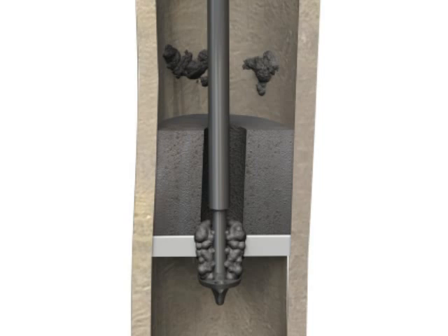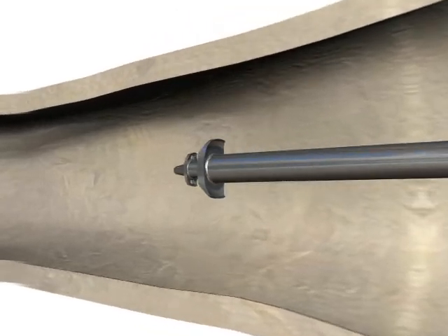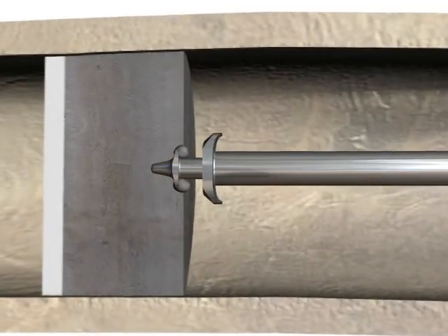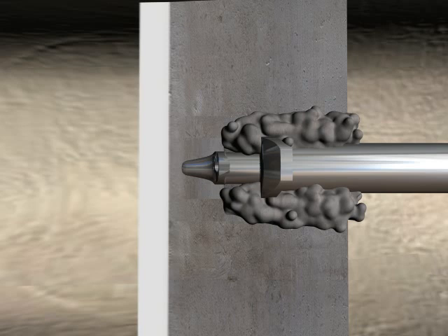For rapid removal of the cement plug under certain conditions, the Oscar system incorporates an extraction probe and slap hammer. The extraction probe, as with the piercer, is designed to penetrate the cement in a forward motion. The surgeon sinks the probe into the plug up to a reasonable depth and then rotates the probe and handpiece through 90 degrees. By removing the power and holding the probe in situ in the canal for 30 seconds, the cement re-hardens around the probe.